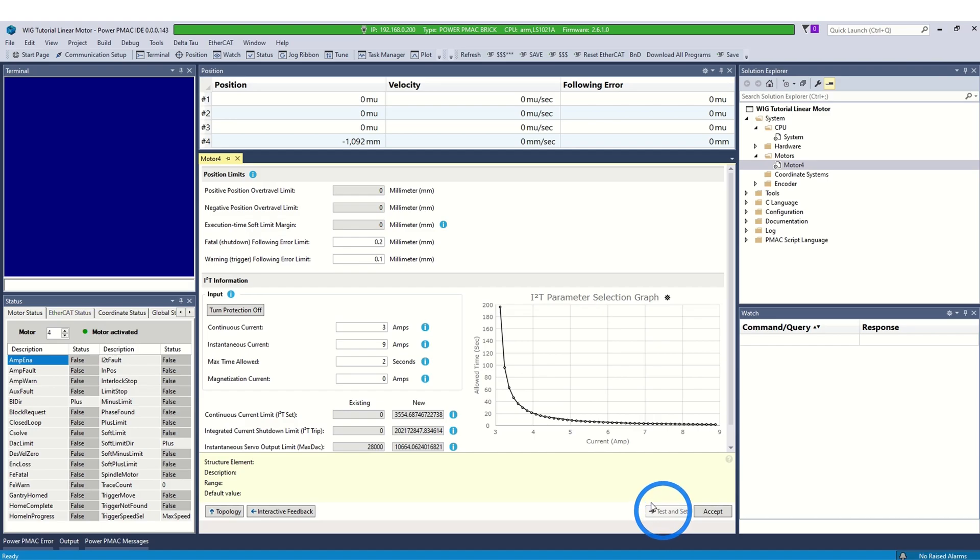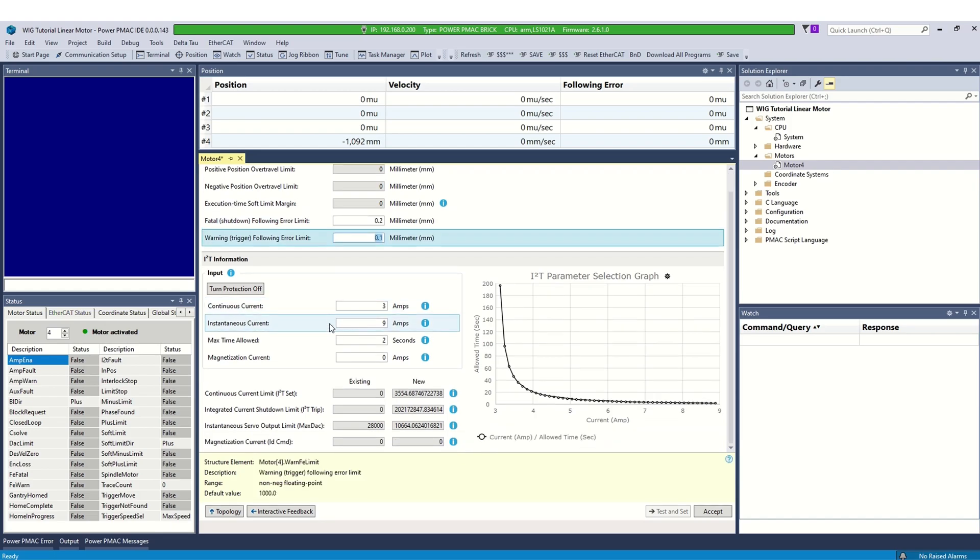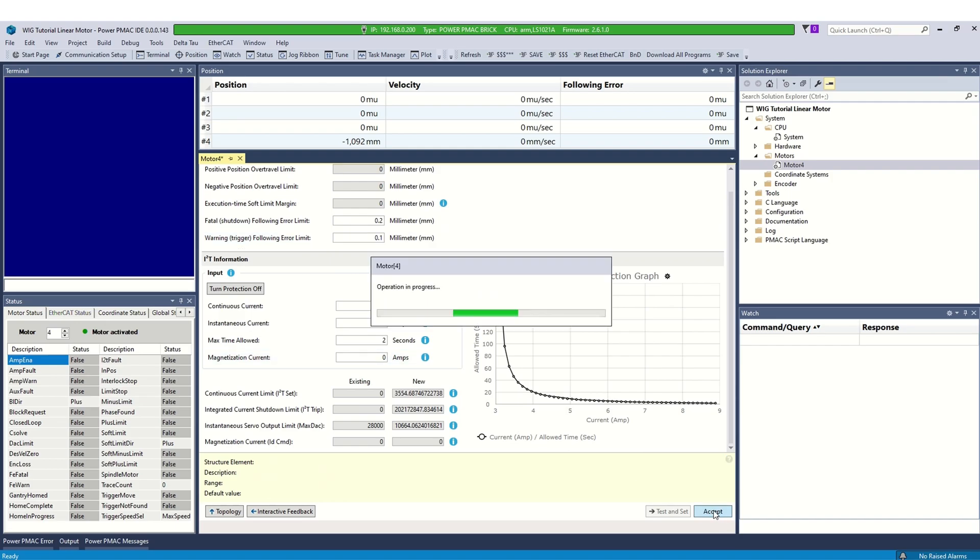Select accept and click on operating limits. On this page, the correct values are already calculated by IDE if you properly filled out motor and amplifier data. The following error limits can be changed according to the system limits. For safety, verify I2T protection limits and make sure they align with the power ratings of the motor and amplifier. If everything looks good, click accept to configure the settings.